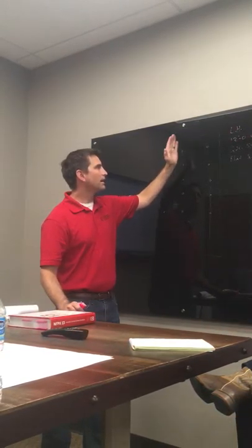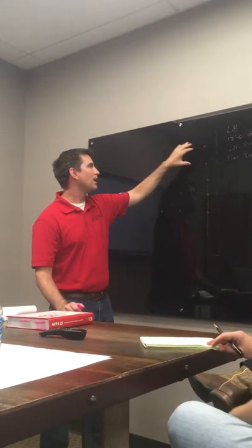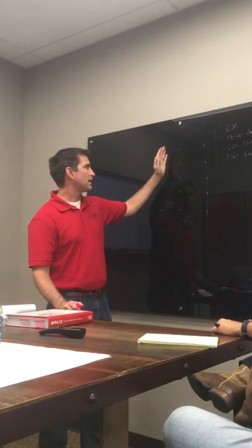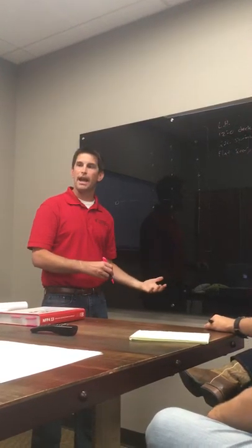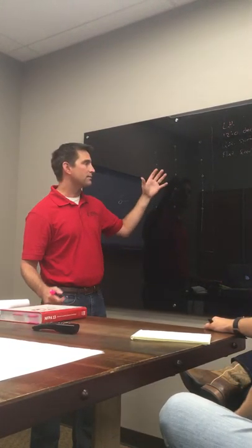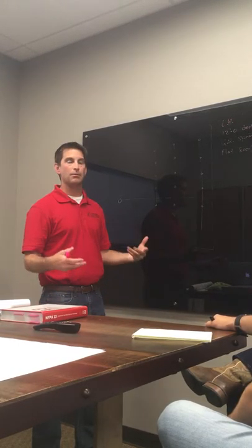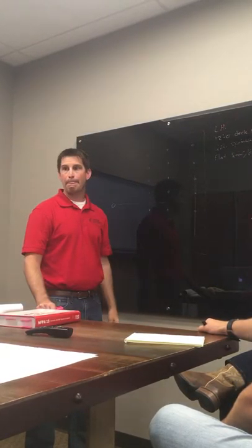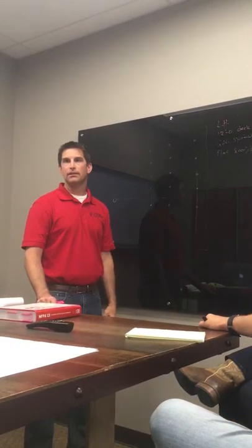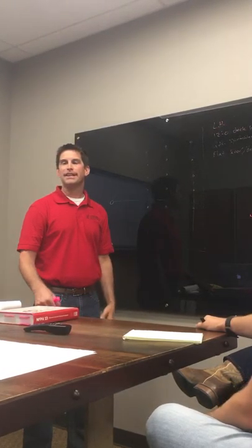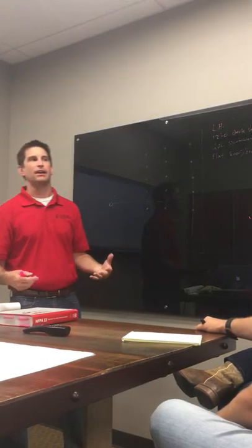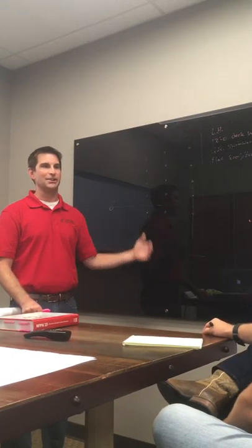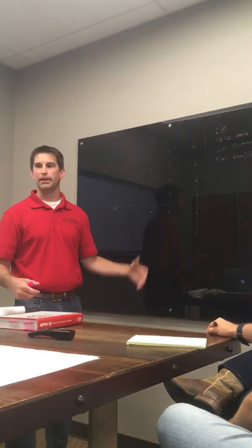So all that's going to happen is the fire is going to grow so big that the heat's going to pop or trigger so many sprinklers. But the code and testing have shown roughly how big a fire could get, based on the hazard and the ceiling heights and everything else, or how many sprinklers it's going to trip. So it's not the area of how big the fire is, just the total number of sprinklers required to put out that fire? Yeah. Or the density, how much water you have to put on it. It's just saying how quick it's going to go and how many sprinklers it's going to trip. And a lot of it's based on testing. They test these scenarios and see how many sprinklers it tripped, or how big the fire got.